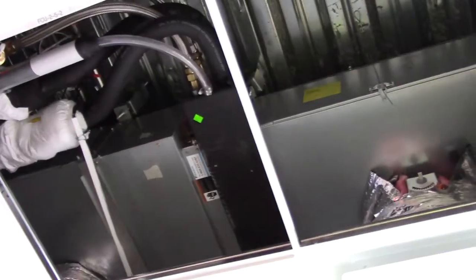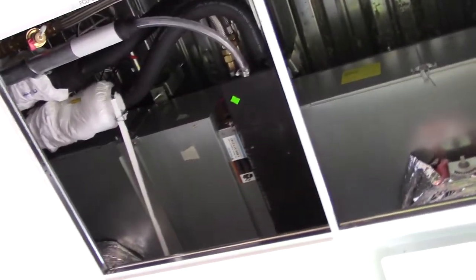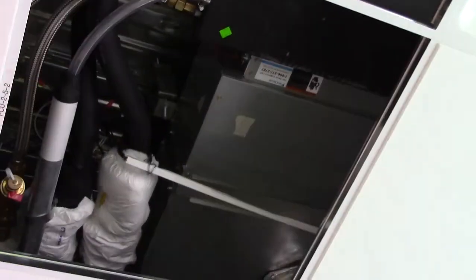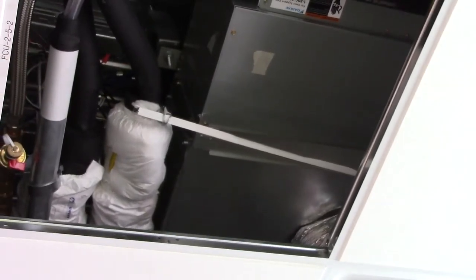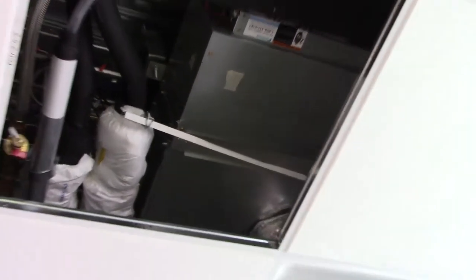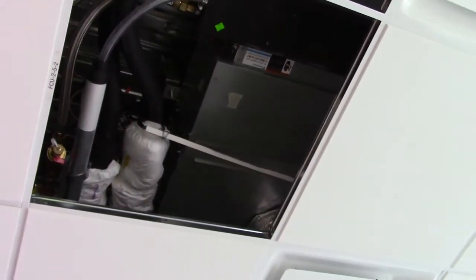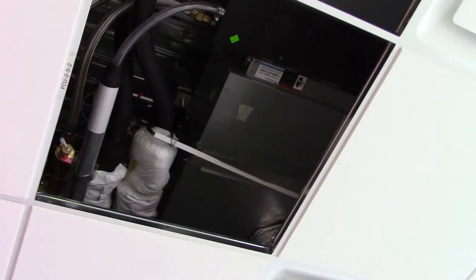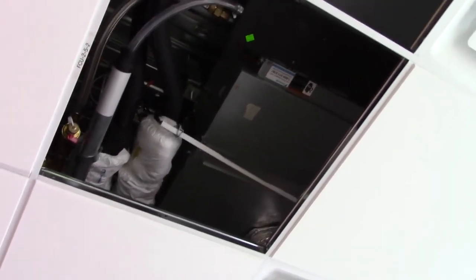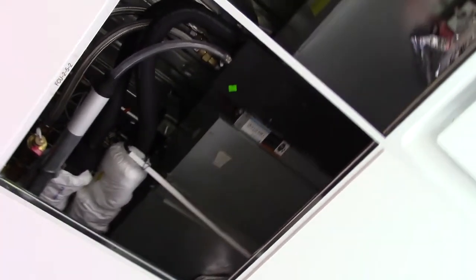On this side, the filter. There's a metal rack side access with two screws, or the bottom drop access for the full length with a couple tabs that you can flip with your hand. The filter should drop down. Blower assembly here before the coil, and the coil and the discharge.